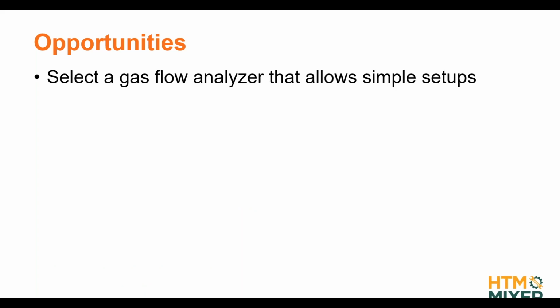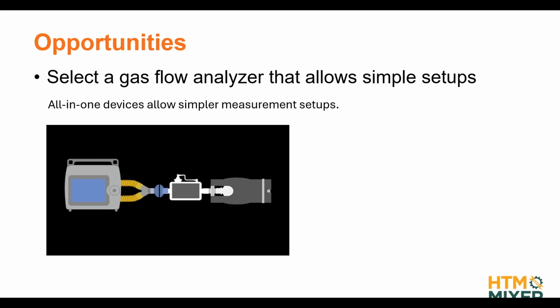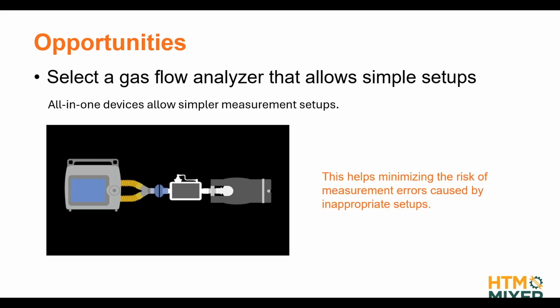The opportunity for manufacturers is to design products that make setups easier, right? And one thing that we always recommend, if you select a gas flow analyzer maybe in the future, is to watch out for what we call all-in-one devices. There are devices out there that measure pretty much everything inside just the flow channel. With devices like that, you just connect the ventilator with the white piece on one side and then the test lung on the other side, and everything else like oxygen, pressure, temperature of the gas, everything that is needed is then measured inside that one flow channel. And of course, this helps minimize the risk of measurement errors caused by setup failures or inappropriate setups.